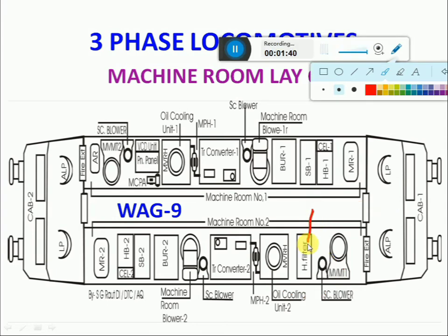Next, harmonic filter. To suppress the harmonics in the traction power circuit. So any high frequencies will be suppressed in the harmonic filter. Harmonic filter is a combination of 3 parts: one is inductor, resistance, capacitor. Resistance was provided on the loco roof, cooled by atmospheric air. This capacitor and inductor are placed in the harmonic filter box.